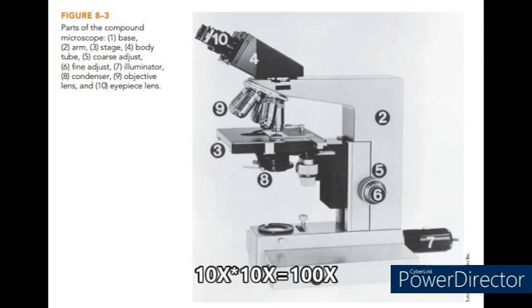A first consideration must be the size of the specimen area, or the field of view, that the examiner wishes to study. As magnifying power increases, the field of view decreases. Thus, it is best first to select a low magnification in which a good general overall view of the specimen is seen, and to switch later to the higher power in which a smaller portion of the specimen can be viewed in more detail. The depth of focus is also a function of magnifying power. After a focus has been achieved on a specimen, the depth of focus defines the thickness of that specimen. Areas above and below this region will be blurred and can be viewed only when the focus is readjusted. Depth of focus decreases as the magnifying power increases.